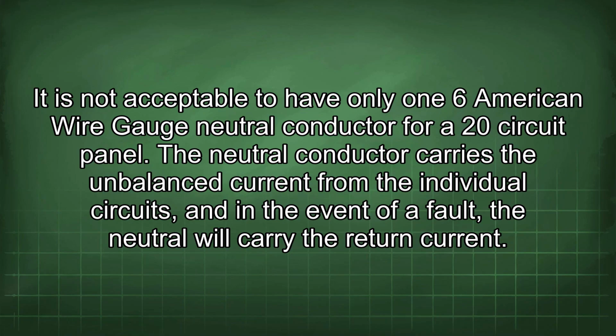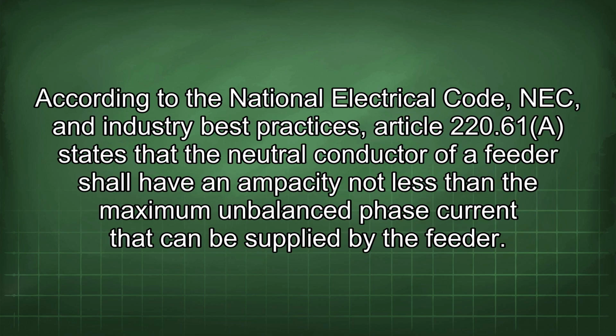It is not acceptable to have only one 6 American wire gauge neutral conductor for a 20-circuit panel. The neutral conductor carries the unbalanced current from the individual circuits, and in the event of a fault, the neutral will carry the return current. According to the National Electrical Code, NEC, and industry best practices, Article 220.61 states that the neutral conductor of a feeder shall have an ampacity not less than the maximum unbalanced phase current that can be supplied by the feeder.